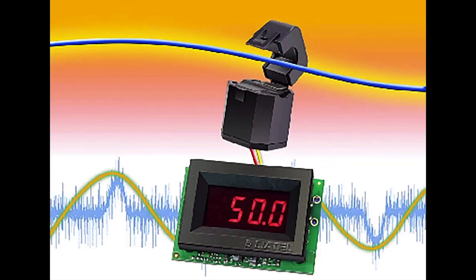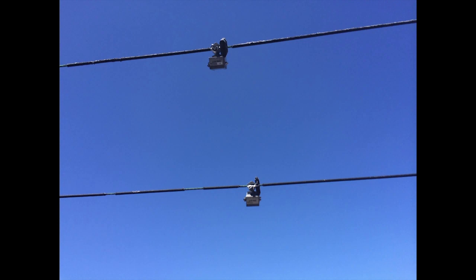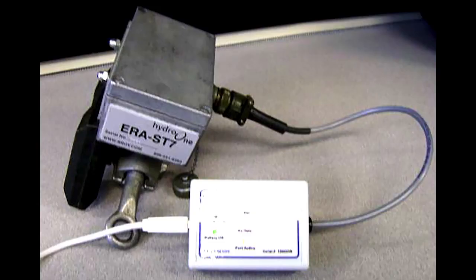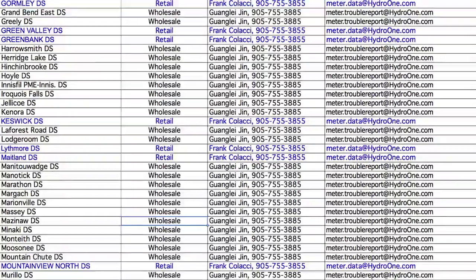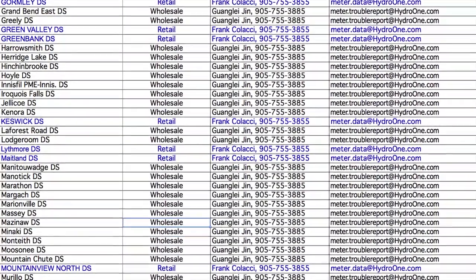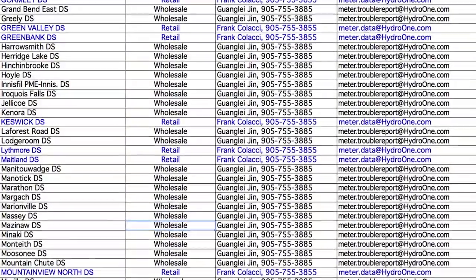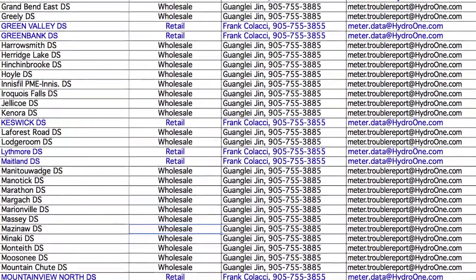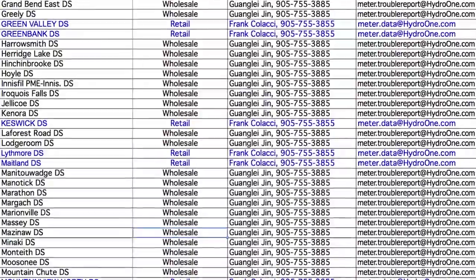An electronic recording ammeter, or ERA, is a portable device that is used to temporarily monitor feeder line currents while the DS is out of service. They are hung on conductors and record the current for 5, 15, or 60-minute intervals, depending on the device setting. This data is stored in the device's memory and downloaded by provincial lines on a weekly basis. Any station listed on the Revenue Metered Distribution Stations list requires ERAs. This list is linked in HODS documents SP 1609 and SP 1610.